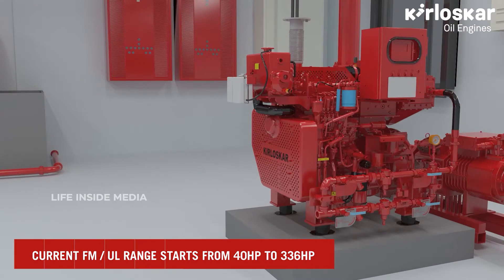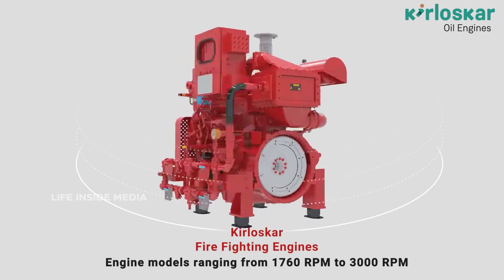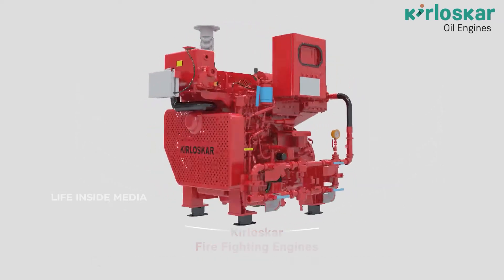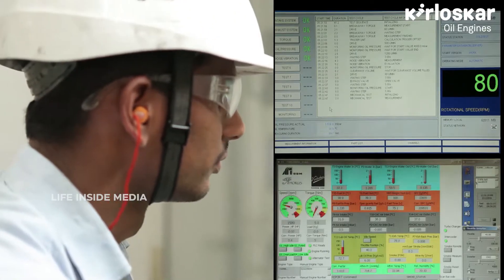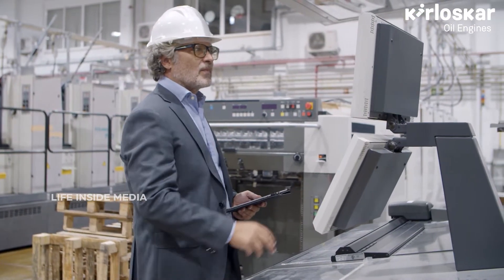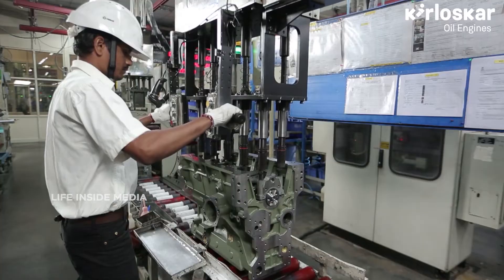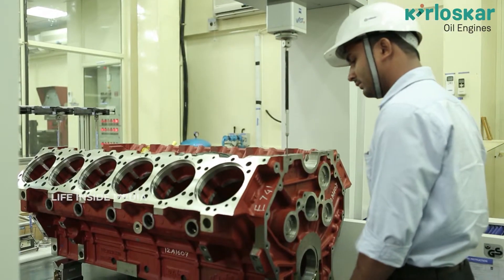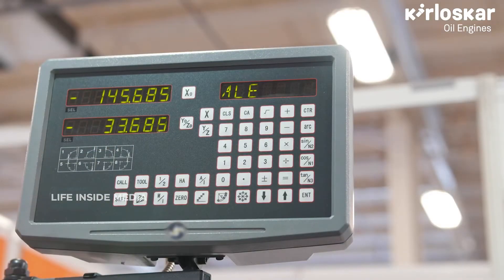The current FM/UL range starts from 40 horsepower to 336 horsepower, with engine models ranging from 1,760 RPM to 3,000 RPM. Our research and development team is working on future extensions in higher horsepower ranges. The stringent approval criteria cover performance and functional requirements, examination of the manufacturing facility, quarterly audits, quality assurance procedures, and a follow-up program to verify proven product conformance.